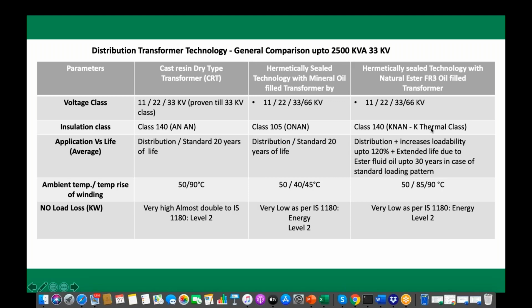A dry type transformer is normally class 140. That's where you limit your temperature rise to 90 degrees over an ambient of 50 degrees C. Mineral oil filled transformers, due to the fluid limitations, are normally class 105, because mineral oil has a lesser thermal class. So that's the reason you limit your temperature rise to 55 degrees C over an ambient of 50 degrees C. And K class fluid transformers are class 140, same as a dry type. That's the reason you can go to a temperature class similar to a dry type transformer.